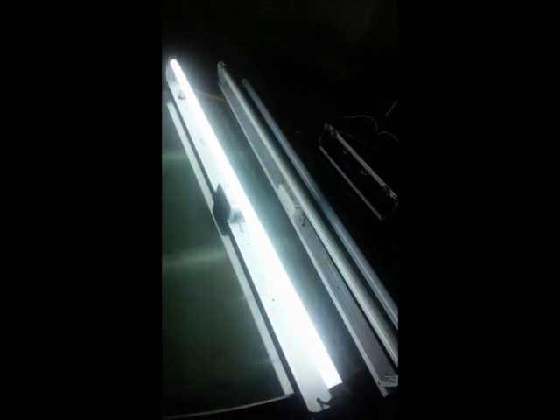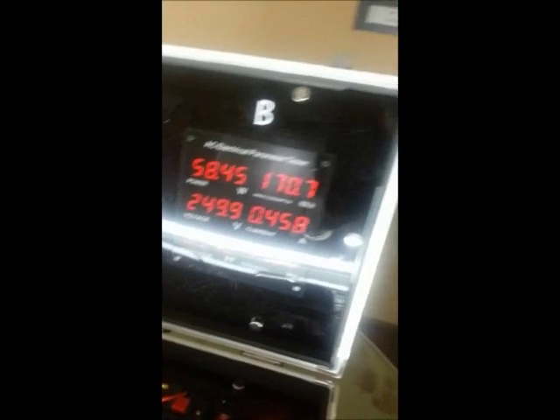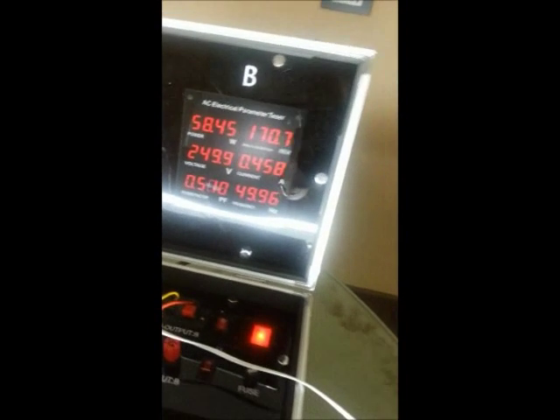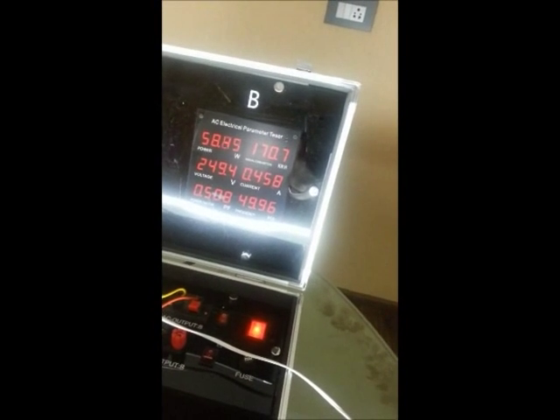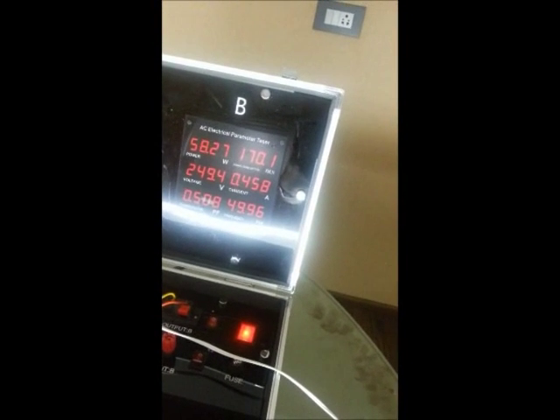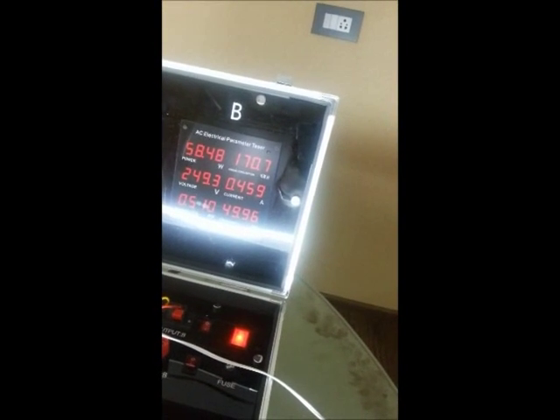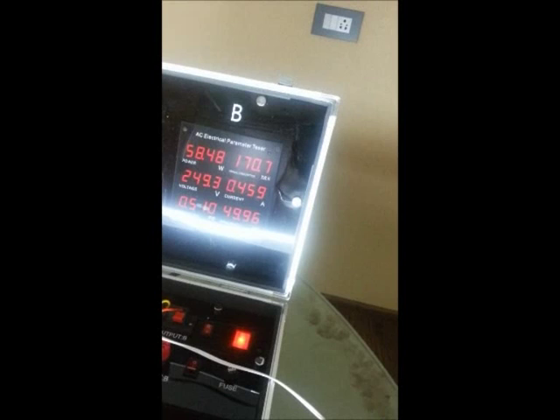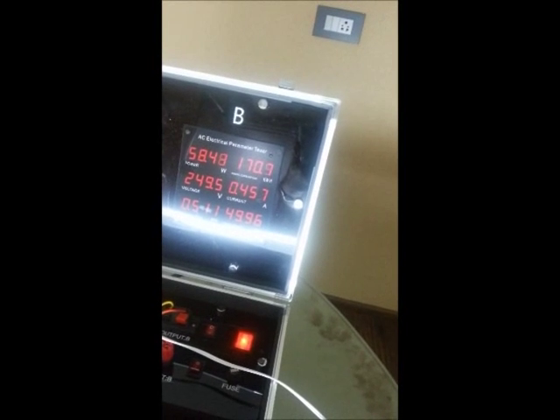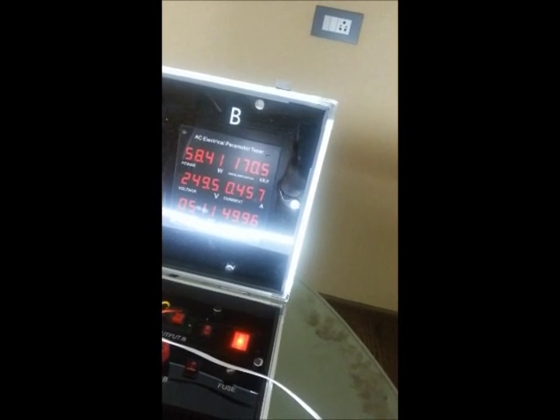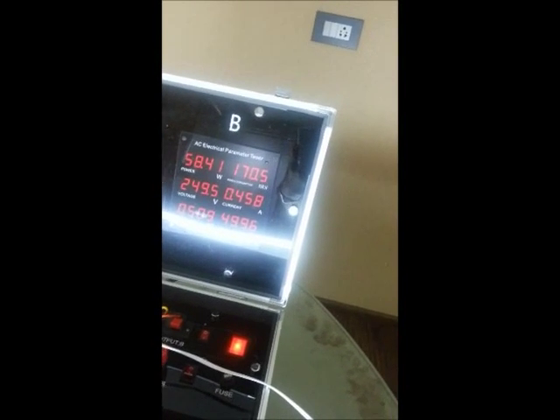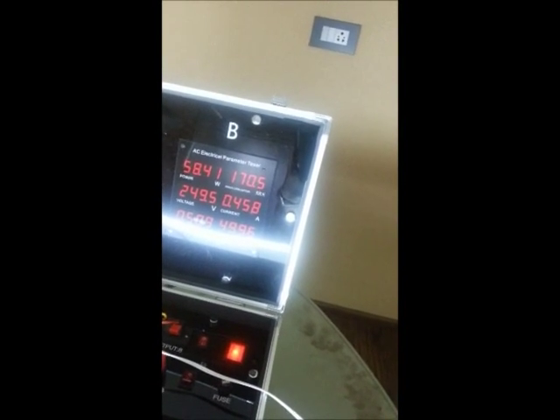Now this is the tube light with a normal choke - you can see here the normal fluorescent tube light. And you can see the power consumption, it is showing as 58.48 watts.